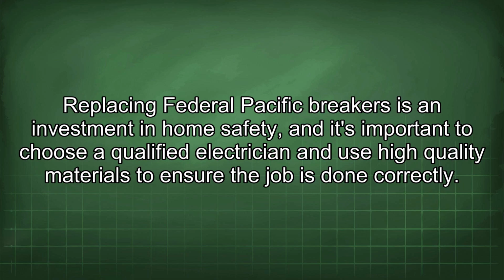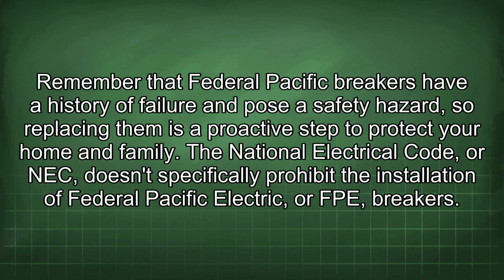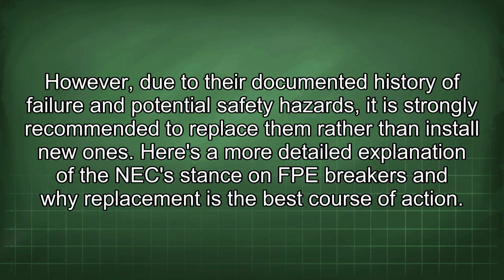Replacing Federal Pacific breakers is an investment in home safety, and it's important to choose a qualified electrician and use high-quality materials to ensure the job is done correctly. Remember that Federal Pacific breakers have a history of failure and pose a safety hazard, so replacing them is a proactive step to protect your home and family. The National Electrical Code, or NEC, doesn't specifically prohibit the installation of Federal Pacific Electric, or FPE breakers. However, due to their documented history of failure and potential safety hazards, it is strongly recommended to replace them rather than install new ones. Here's a more detailed explanation of the NEC stance on FPE breakers and why replacement is the best course of action.